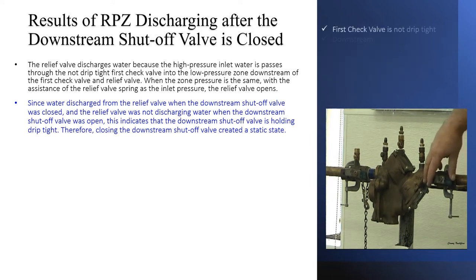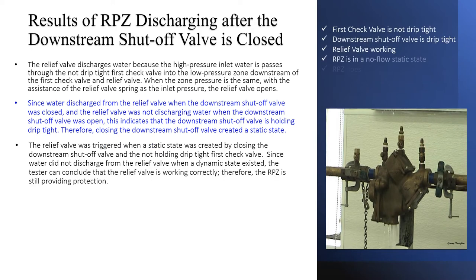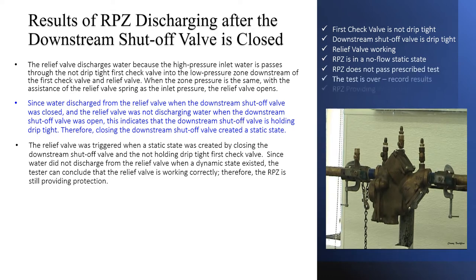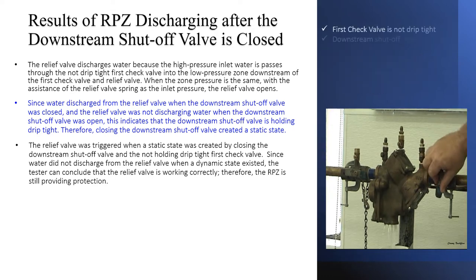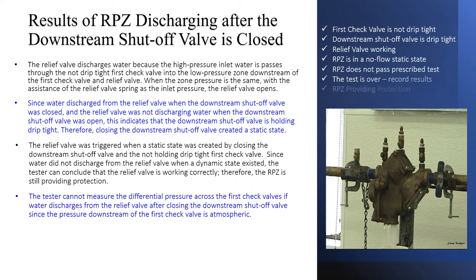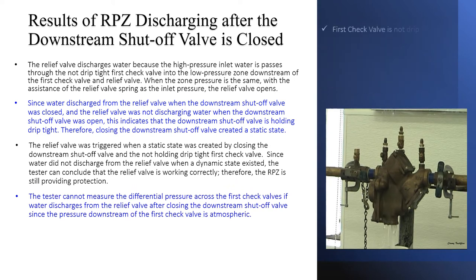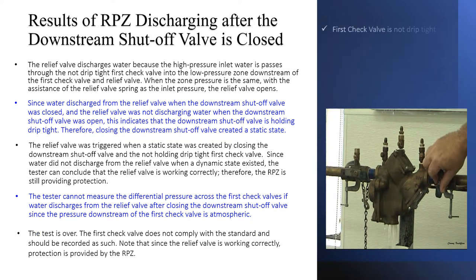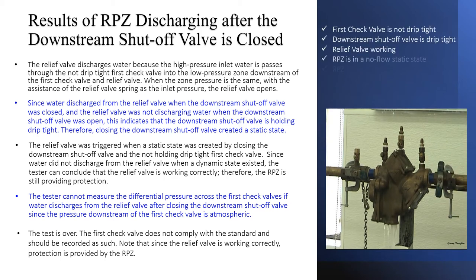Therefore, closing the downstream shutoff valve created a static state. The relief valve was triggered when a static state was created by closing the downstream shutoff valve and the not-drip-tight first check valve. Since water did not discharge from the relief valve when a dynamic state existed, the tester can conclude that the relief valve is working correctly, and the RPZ is still providing protection. The tester cannot measure the differential pressure across the first check valve if water is discharging from the relief valve after closing the downstream shutoff valve, since the pressure downstream of the first check valve is atmospheric. The test is over. The first check valve does not comply with the standard and should be recorded as such. Note that since the relief valve is working correctly, protection is provided by the RPZ.